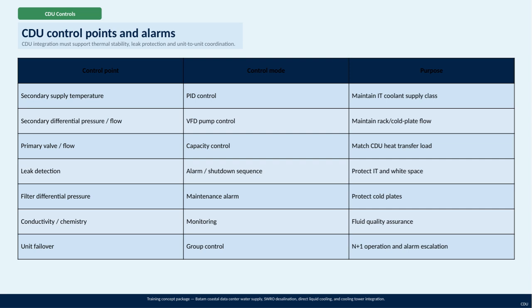Leak detection acts as a safety mechanism, triggering alarms or even shutdown sequences to protect both the IT equipment and the surrounding white space from damage. Filter differential pressure is monitored to signal when maintenance is needed, protecting the cold plates by ensuring filters remain effective. Conductivity and chemistry parameters are continuously monitored for fluid quality assurance, helping prevent corrosion or contamination. Finally, unit failover is handled through group control, supporting N+1 operation to maintain system reliability and escalate alarms as needed.